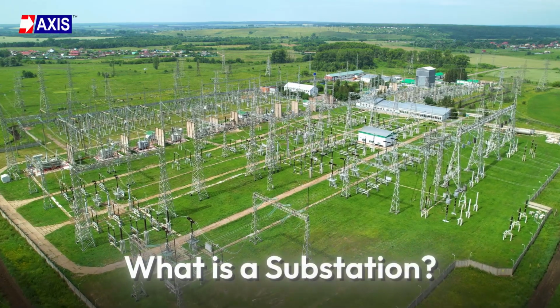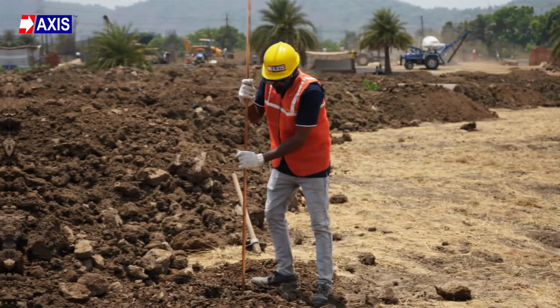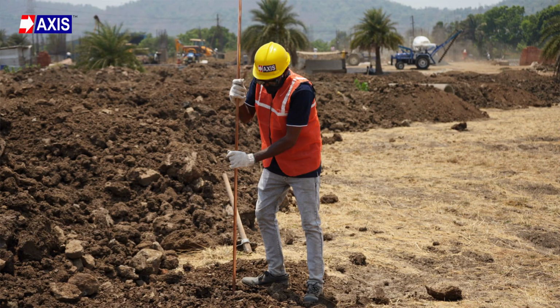So let's start with the basics. What is a substation? A substation is a point in the power system where voltage is transformed, controlled, and distributed. Think of it as the gateway between the high voltage transmission network and the end users who consume the power. Now, within that substation, every metal structure and every piece of equipment needs to be connected to the earth. This is done through a process called substation earthing. When a fault occurs, it gives that fault current a safe and controlled path into the ground, protecting both the equipment and the people working around it.